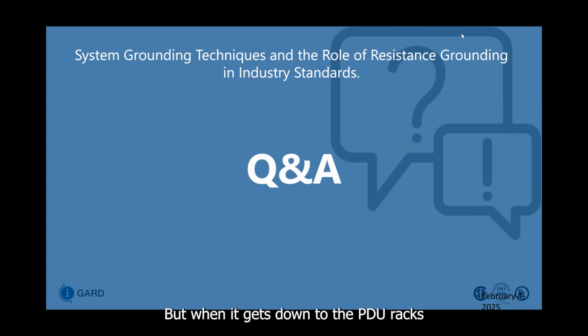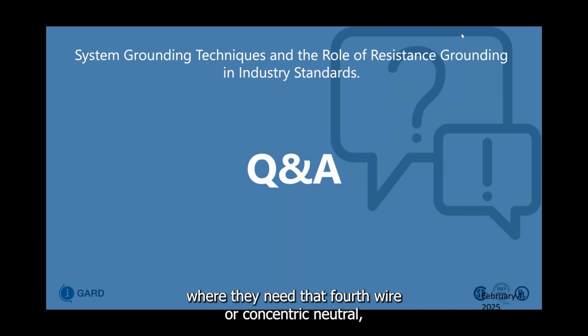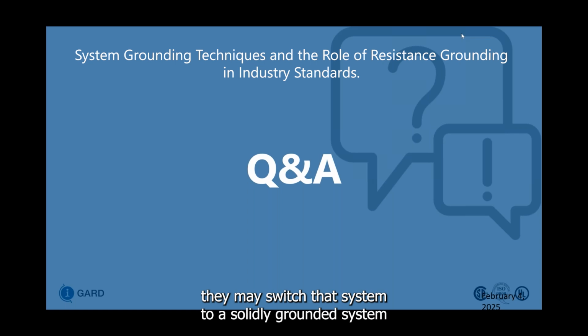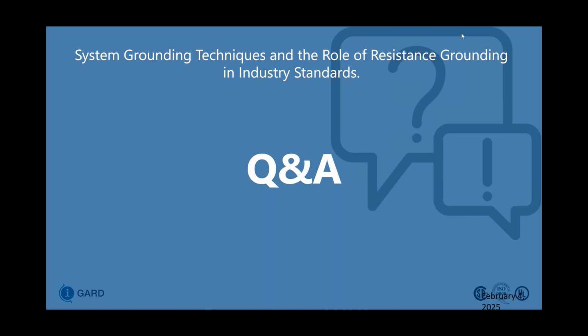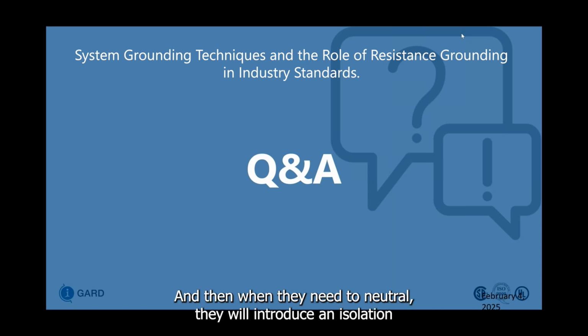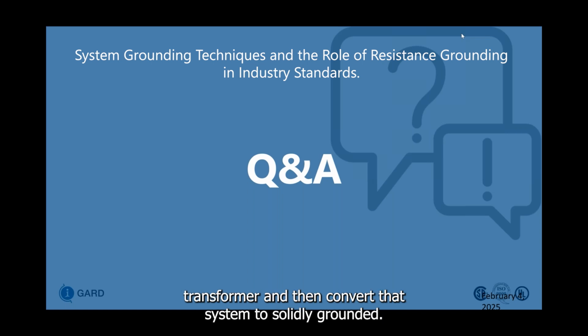But when it gets down to the PDU racks where they need that fourth wire or a concentric neutral, they may switch that system to a solidly grounded system because they have single phase loads to satisfy. So on the upper level, they will have on their three-phase three-wire setups high resistance grounding, and then when they need the neutral, they will introduce an isolation transformer and then convert that system to solidly grounded.